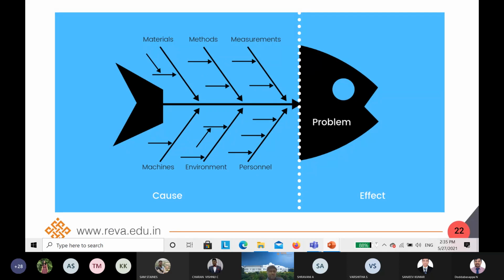Whether it was giving more temperature at that time, how it was cooling, whether you noted how much volume of oil was there - correct? The pressure and quantity of oil, whether flow of oil was stuck, everything you should measure. What was the reading the previous day, what was the reading on that day, readings over the previous one week - those are all the measurements.